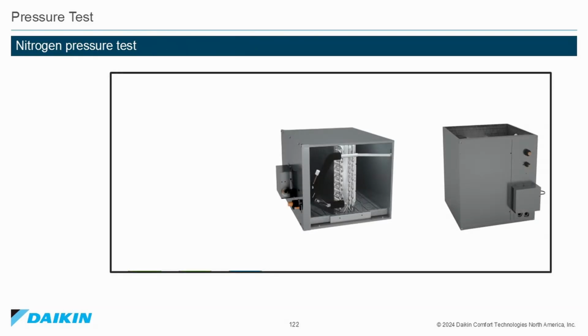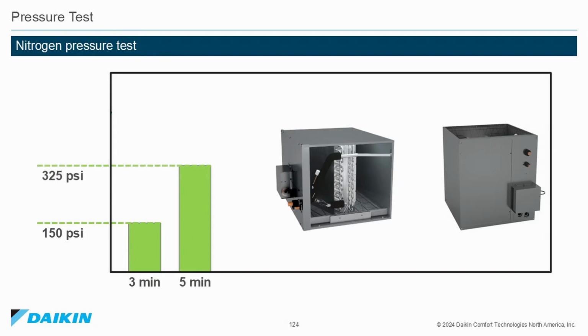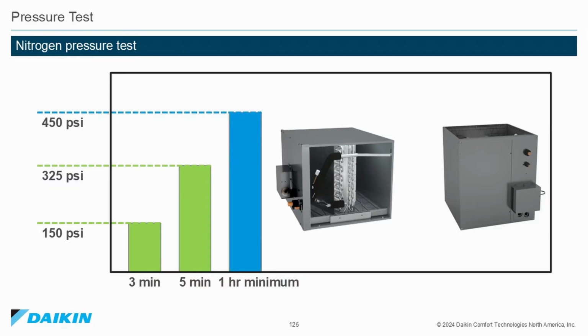When performing the nitrogen pressure test, it is recommended that you pressurize the system to 150 psi and allow it to stand for 3 minutes. Increase the pressure to 325 psi and allow that to remain for 5 minutes. Then increase the pressure to 450 pounds and leave that in the system for a minimum of 1 hour.